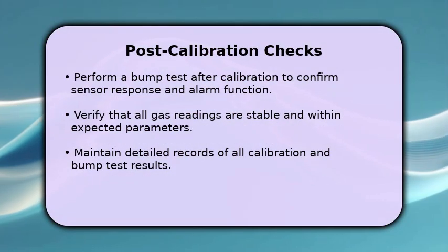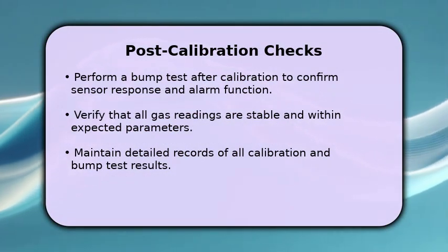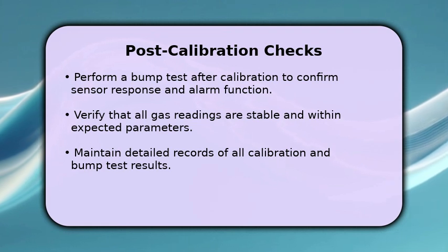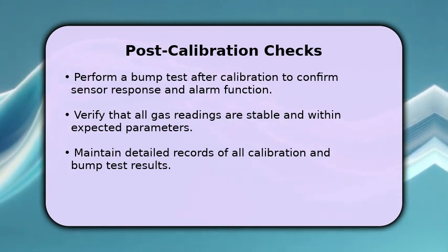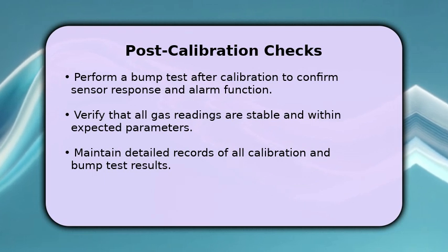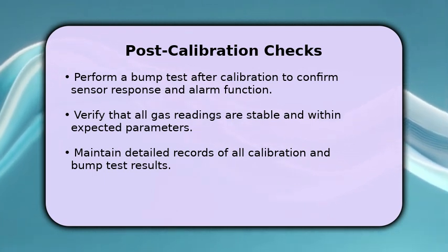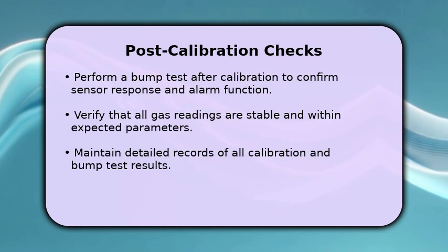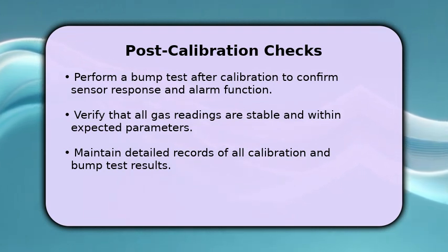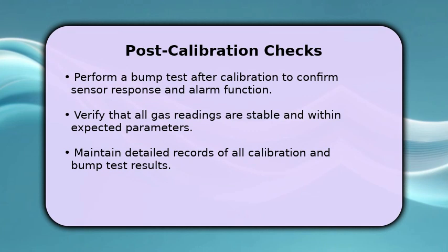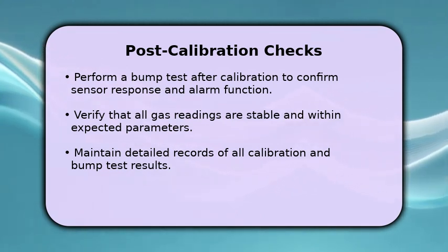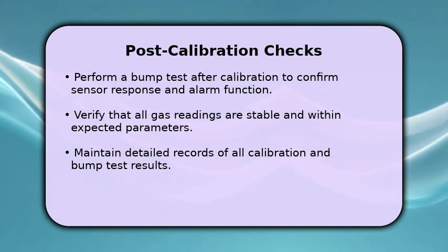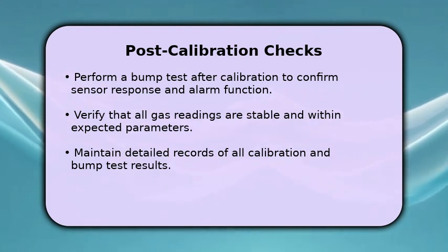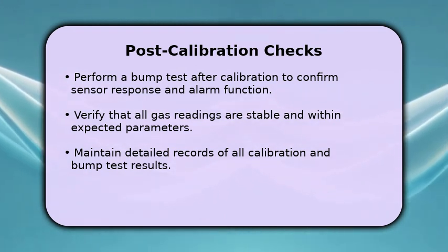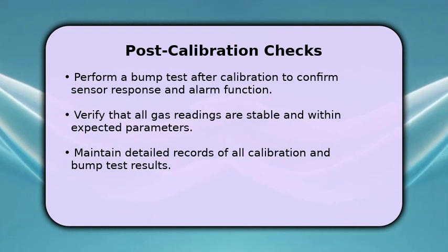After completing both zero and span calibration, it is highly recommended to perform a bump test. This quick test, typically lasting about 15 seconds, verifies that all sensors respond correctly to gas and that the audible, visual, and vibrating alarms are fully functional. Always check that your gas readings are stable and accurate. Remember to keep thorough records of all calibration and bump test results for compliance and future reference, ensuring your GMI PS200 remains reliable.